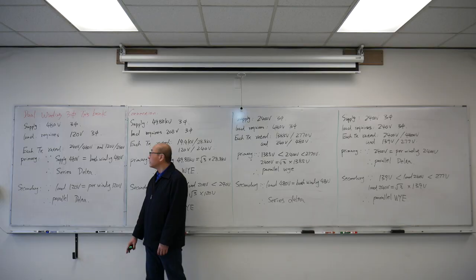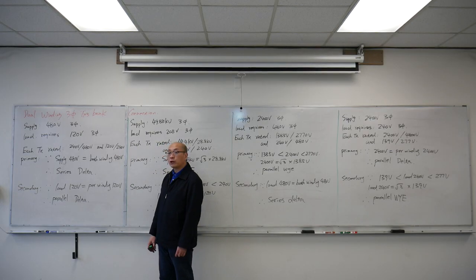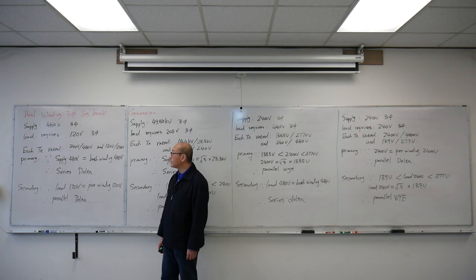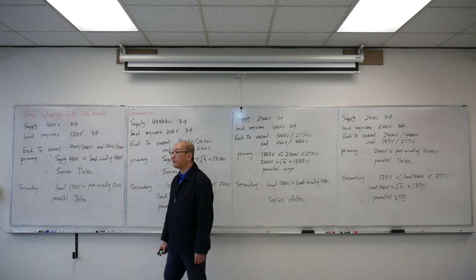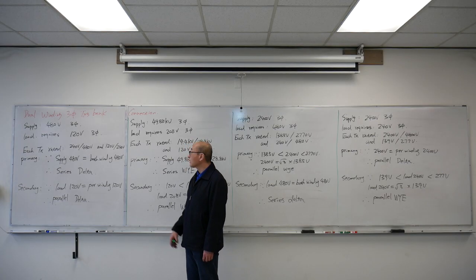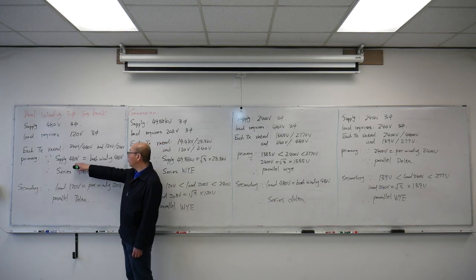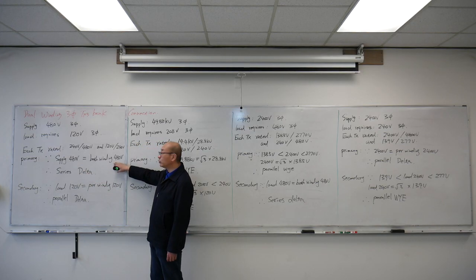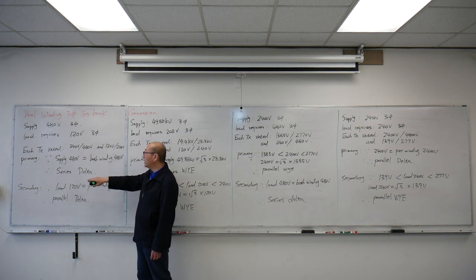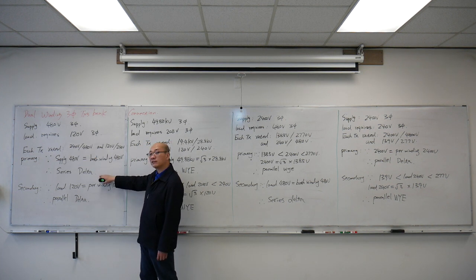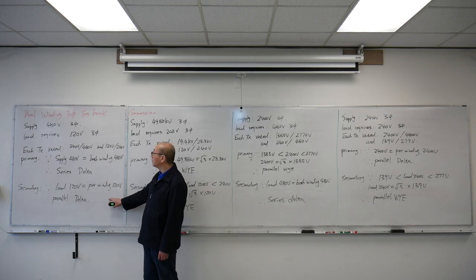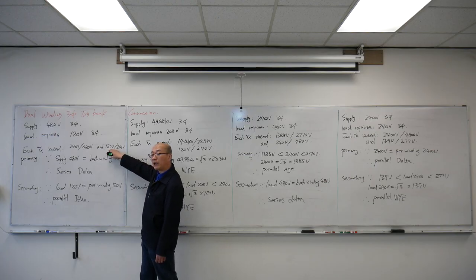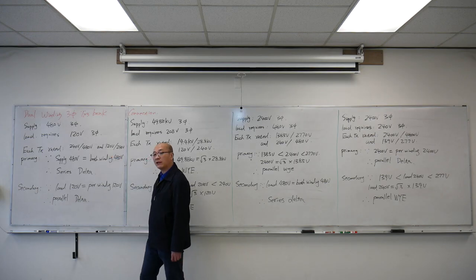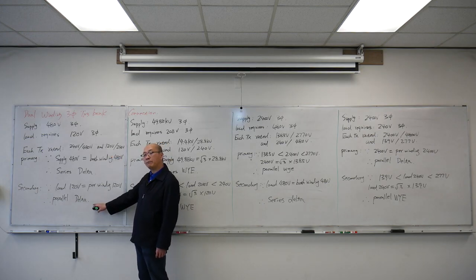The first example: our supply is 480 volts. The load requires 120 volts. They're both three-phase. The transformer is rated for 240 volt, 480 volts on the high voltage side, and 120, 240 on the low voltage side. Because the supply of 480 volts is equal to the both winding voltage, 480 volts down here, I know the primary is going to connect in series delta. On the secondary side, the load requires 120 volts. 120 volt is equal to the per winding voltage down here, so I know my secondary side is going to connect in parallel delta.